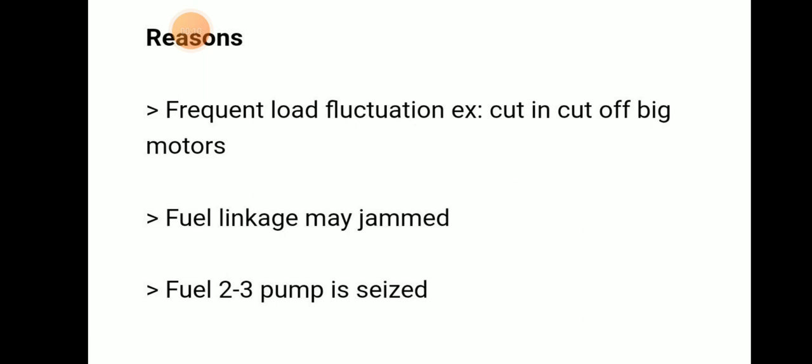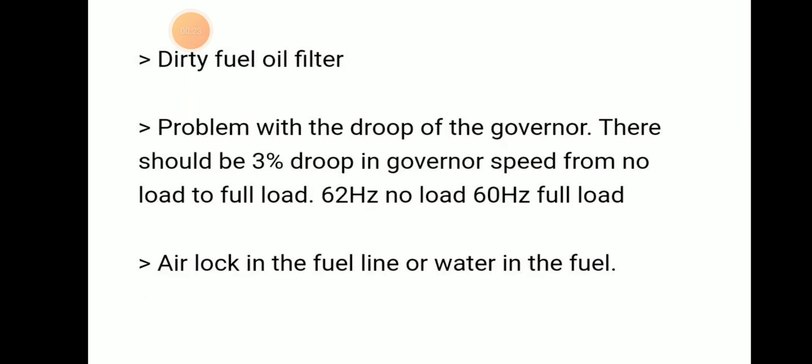The main reasons are frequent load fluctuations — for example, the cut-in and cut-off of big motors. Also, fuel linkage may be jammed, 2 or 3 fuel pumps may be seized, or there may be a dirty oil filter.